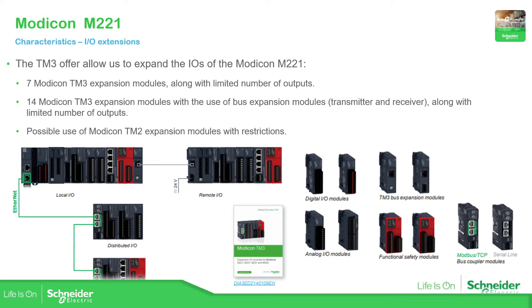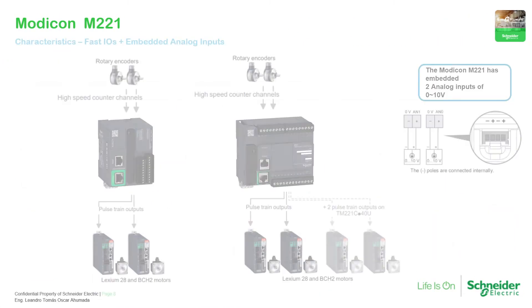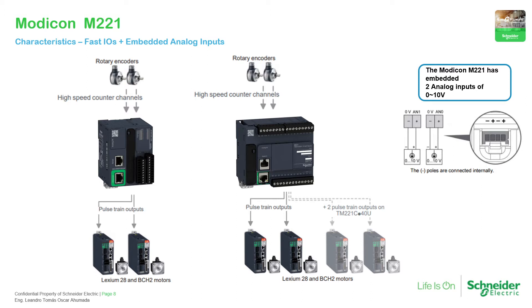Another characteristic of this PLC is the fast inputs and outputs. We have the possibility to use encoders with the high speed counter (HSC), which operates up to 100 kHz. We can also use sensors for a single-channel fast speed counter. Additionally, we can use the PTO (Pulse Train Output) of this PLC — for example to communicate with servo drives such as the Lexium 28 using PTO pulses.